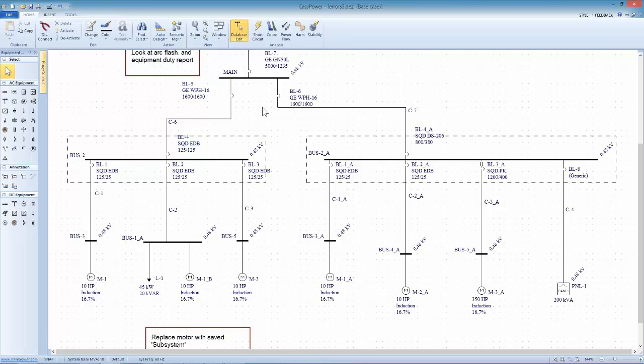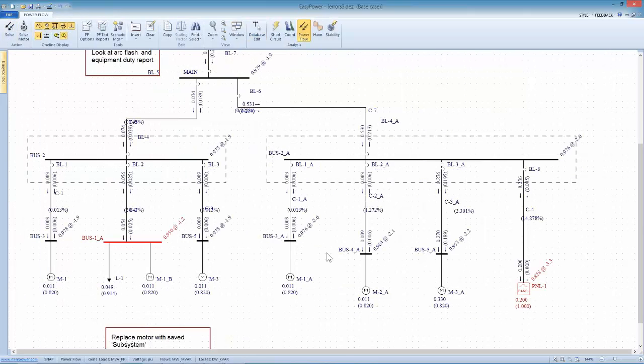The final one: as we do studies, because we assist customers to do arc flash studies as a support to tool owners, very frequently, if we're involved in the data collection side of the equation, we will take voltage readings on any part of the system that's powered up as we're collecting data. What we're doing as you're building this one-line diagram is literally modeling an ideal depiction of what your system is.